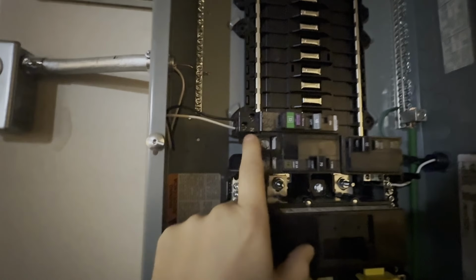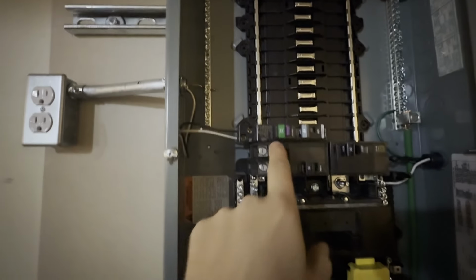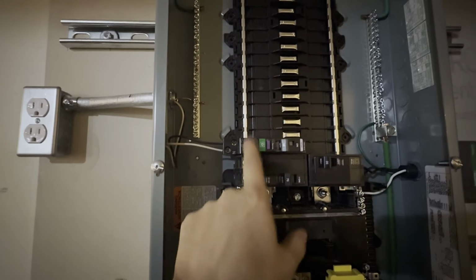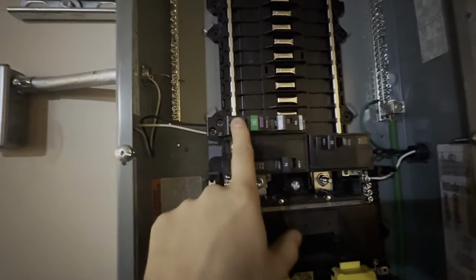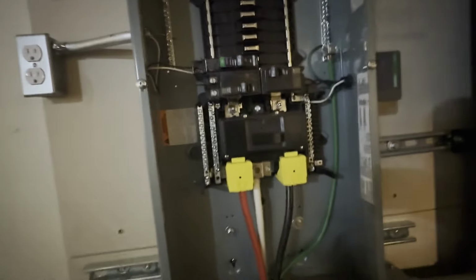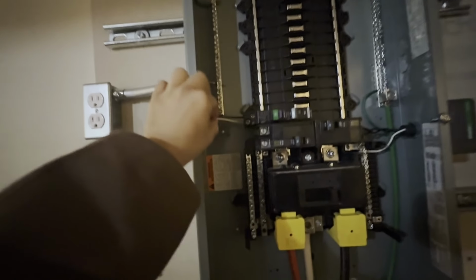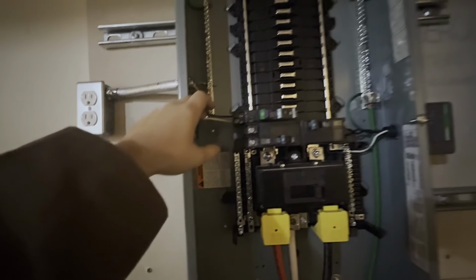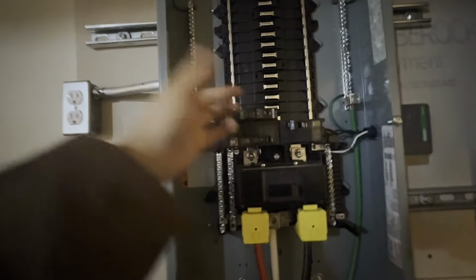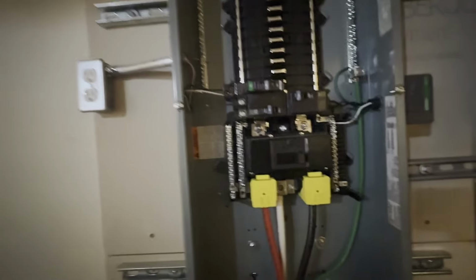It's got plug-on neutral, which means it's for AFCI and GFCI breakers like this. I don't actually have to put the neutral to the neutral bars or the ground bar. It goes into the breaker, and AFCI and GFCI, that's arc fault and ground fault. So if there's a break in the wire or something and it's arcing, this will detect it and turn off. If there's a ground fault, i.e., the toaster in the bathtub problem, it'll trip. Hopefully save you from that. Don't try it. But yeah, these are neat.